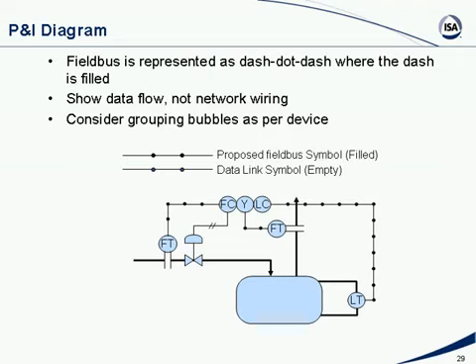Another thing people fret over is, if I do control in the field and I have the PID, how do I show where the PID is located? One way, if the PID is done in the valve positioner, which is probably the most common way, is to simply draw the PID bubble adjacent to the valve positioner bubble, so you intuitively understand the PID is together with the valve positioner. Keep in mind that in a P&I diagram you want to show data flow, not the physical bus wiring, otherwise it becomes too cluttered if you try to mix field bus wiring into the P&I diagram. So stay away from that.